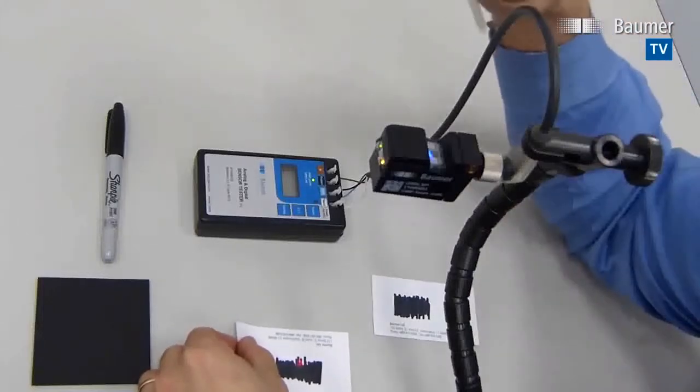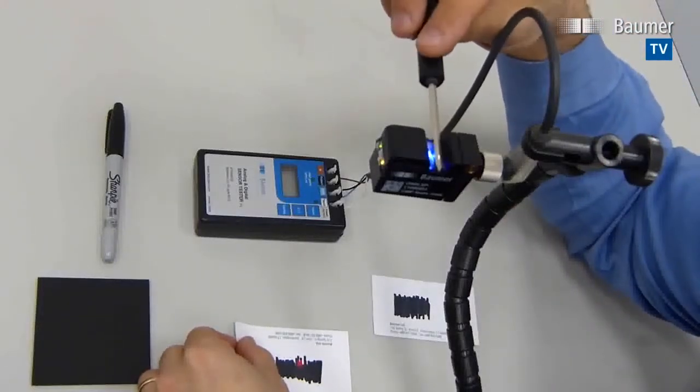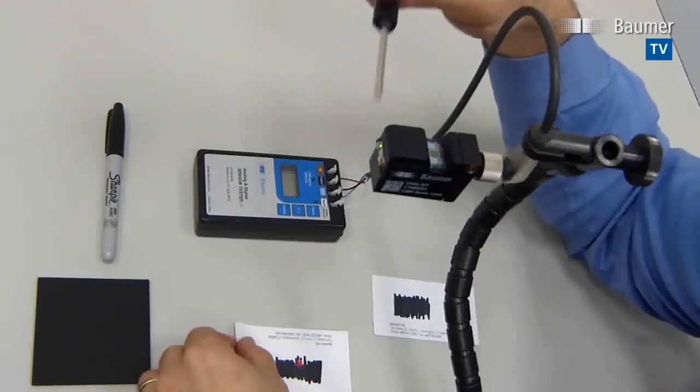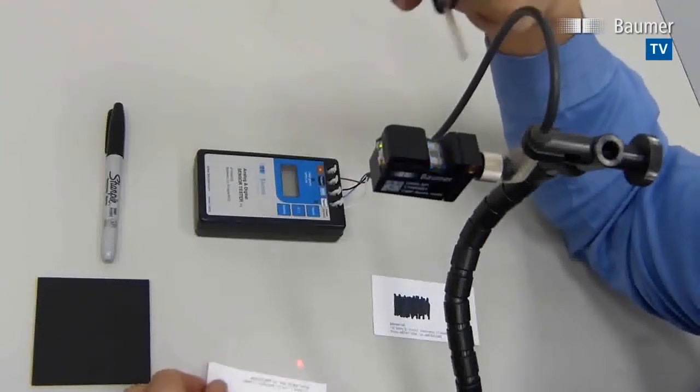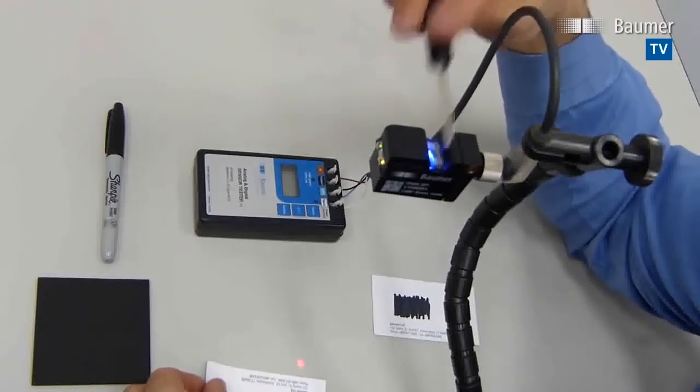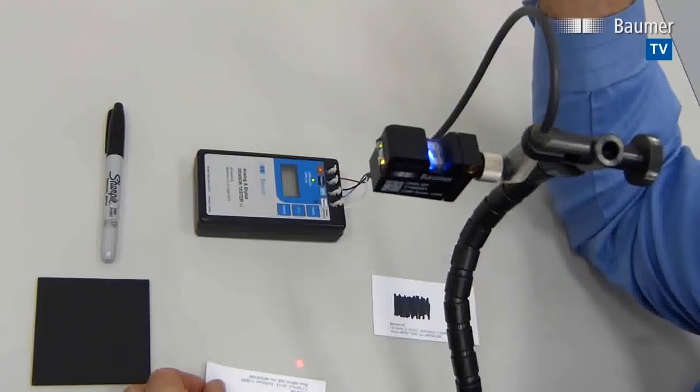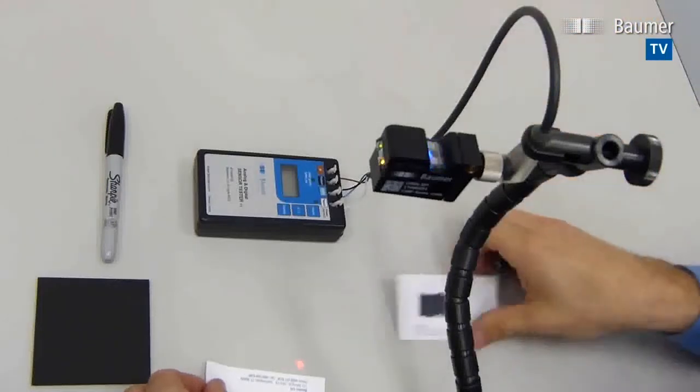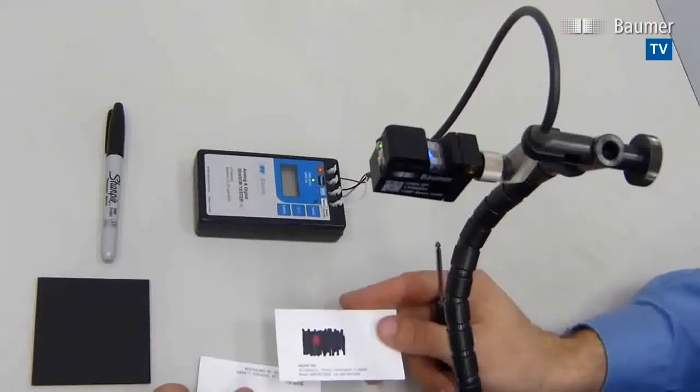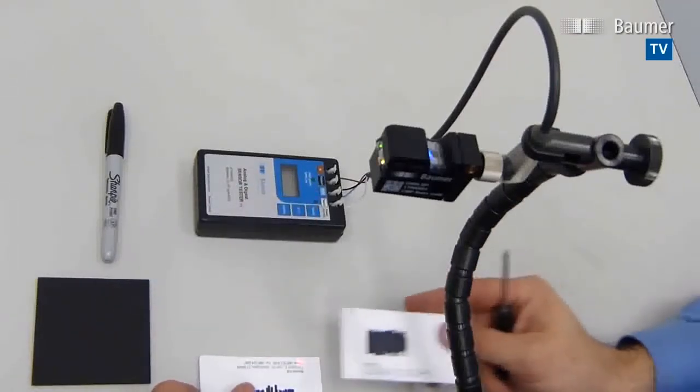We can change that mode by the way we teach it. Again, we enter teach mode by holding the QTeach function until these begin to flash. And then we show the sensor the background. And within four seconds, we show the background again. And now, the sensor will give that green PNP output when the beam is blocked.